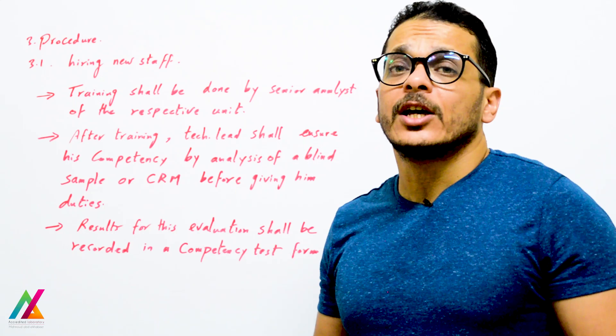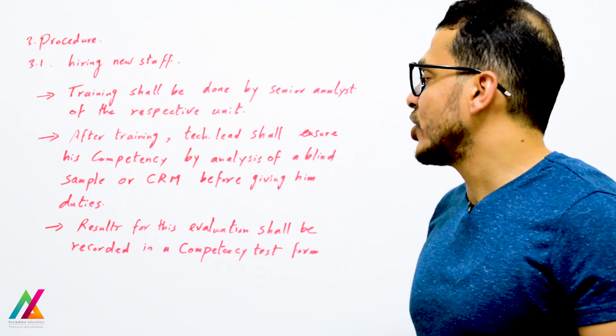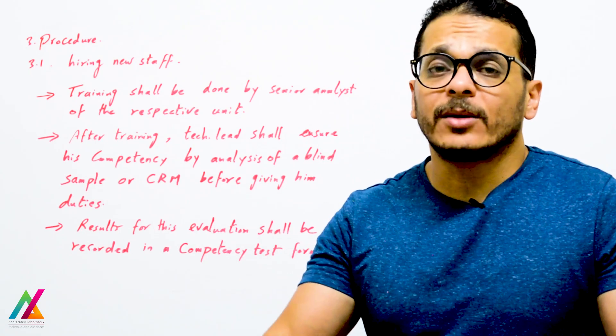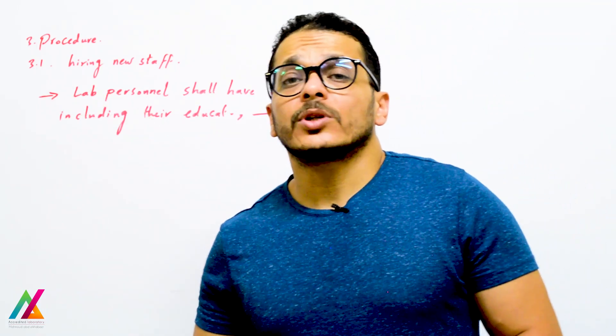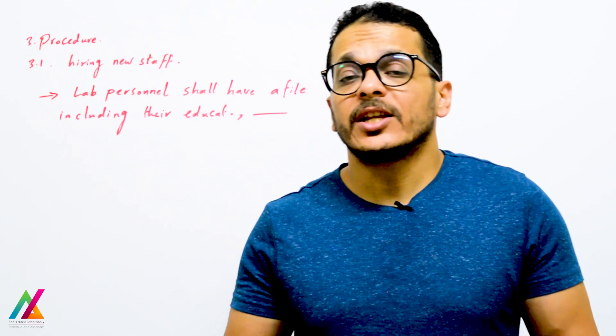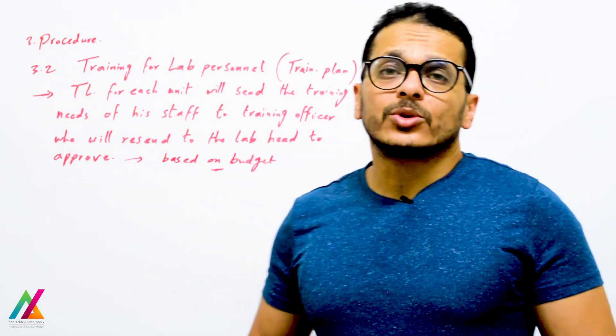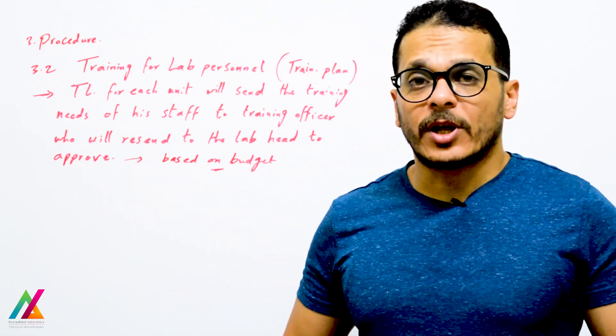After training, competency shall be technically evaluated by giving the analyst a blind sample with unknown concentrations of target analytes, or a certified reference material containing the target analytes — before assigning any duties. Results of this evaluation shall be recorded in a competency test form. To receive duties, results must be within the acceptable range. Every person inside the lab shall also have a personal file including education certificates, training certificates, and any other relevant certificates.